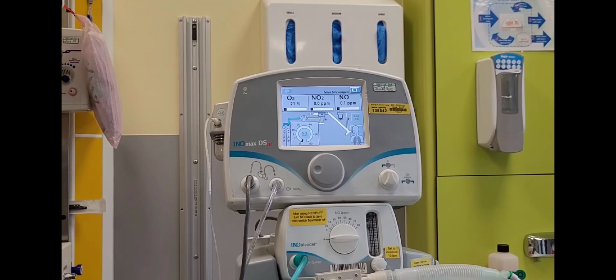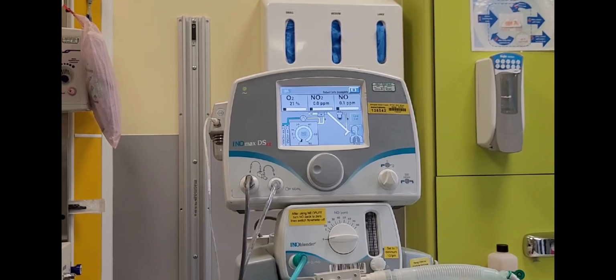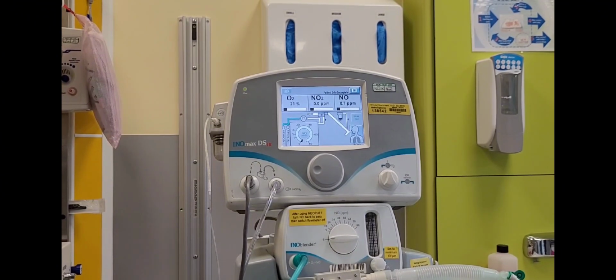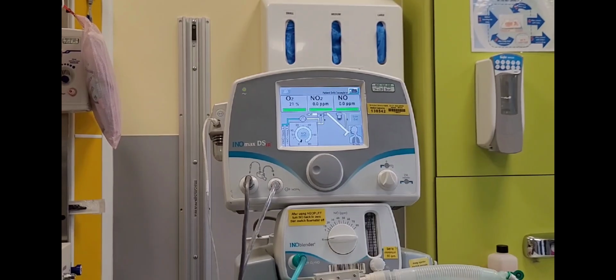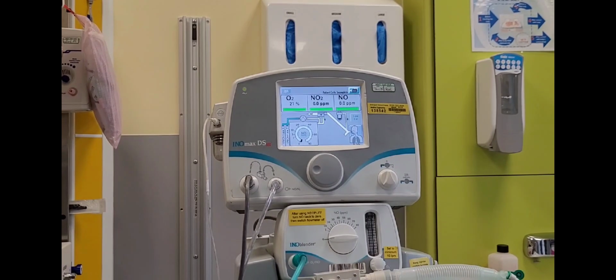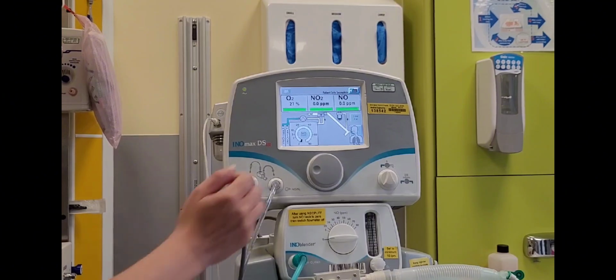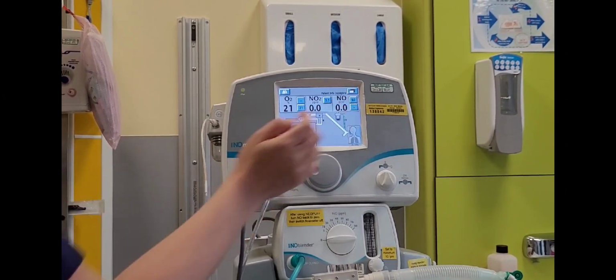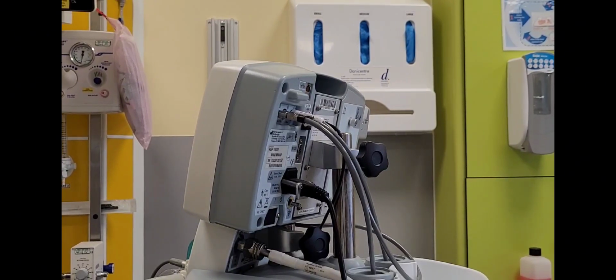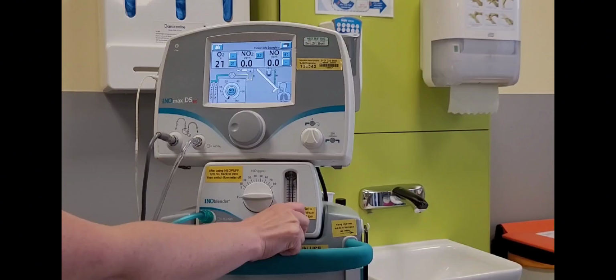There are 2 troubleshooting things to do here. Double check that the cylinders are tightly turned off and you cannot see any numbers displayed on the top. If this does not work, you can purge the nitric lines. Once the bars are turned green, you know that your low range calibration is successful. Make sure that the nitric lines are connected at the back here, in case your calibration fails.